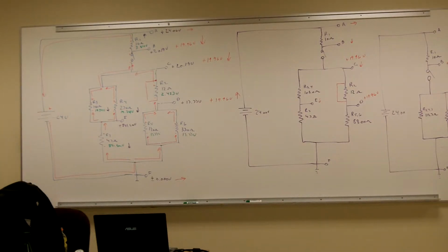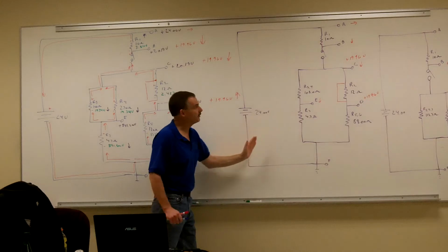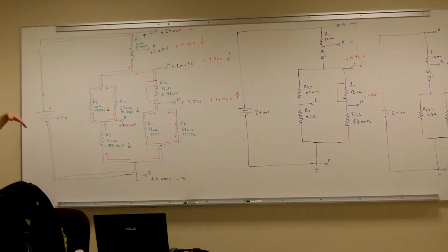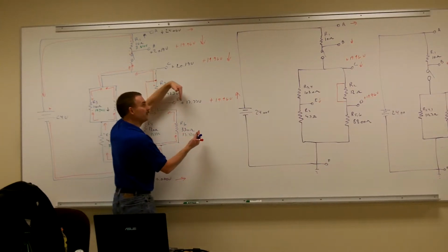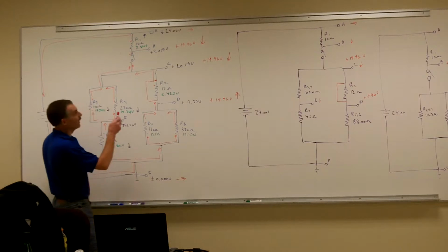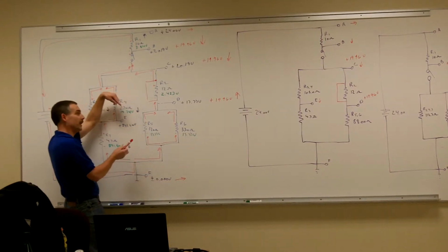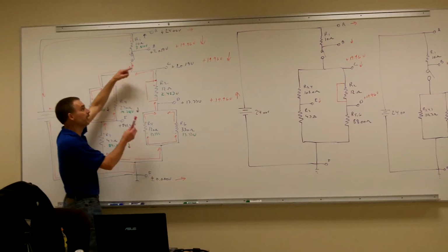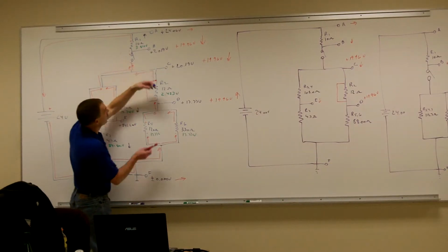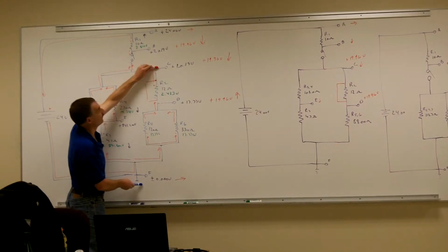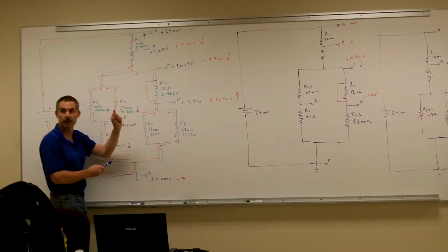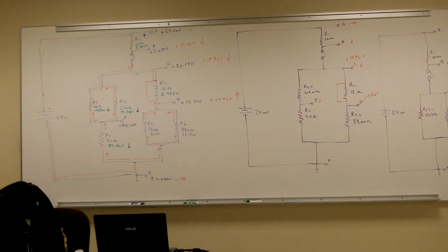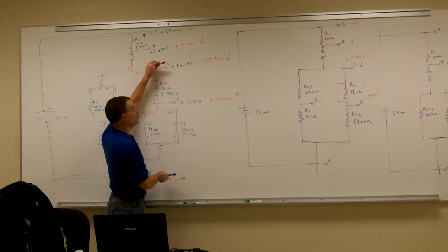Okay? When I'm doing this, it looks obvious to me because I already know some of the tricks and techniques. Like yesterday when I was doing the speed rush, I knew exactly what was supposed to happen, because I was doing the arrow method. I already knew that as long as I'm measuring across the short, my voltage is going to go down. The minute I went to the opposite side of that short, I knew that voltage was going to go up, just because it always happens. It's one of those routine things you can do to double check your work. As I said, there are always ways to double check your work.